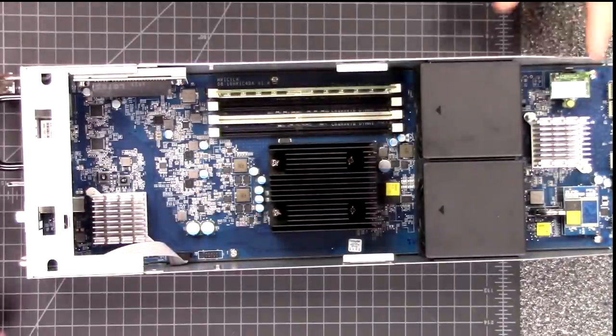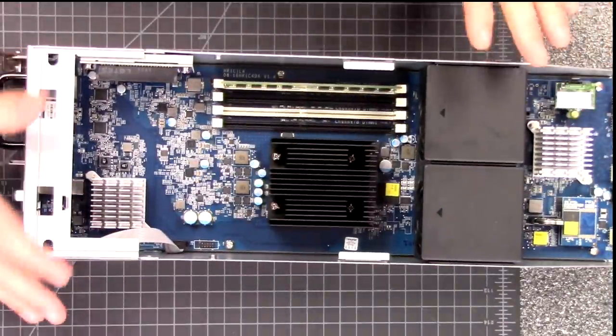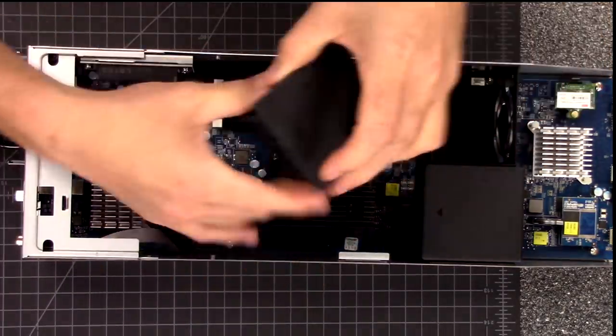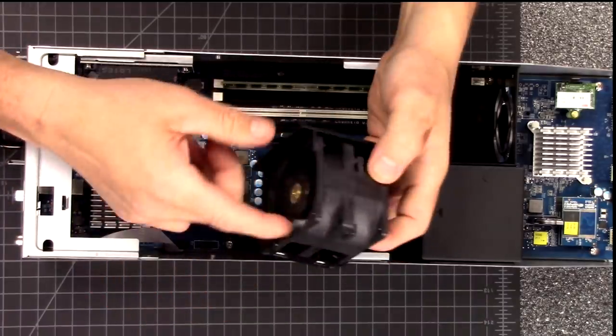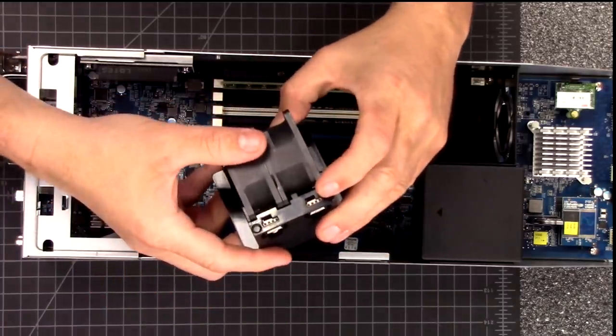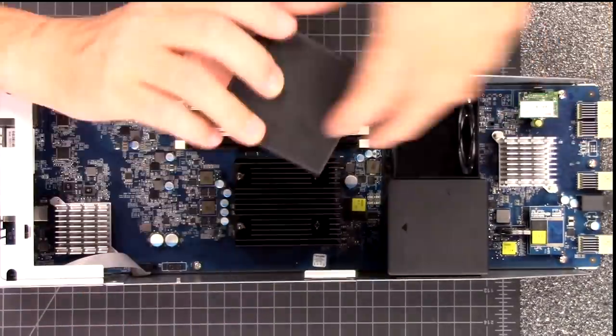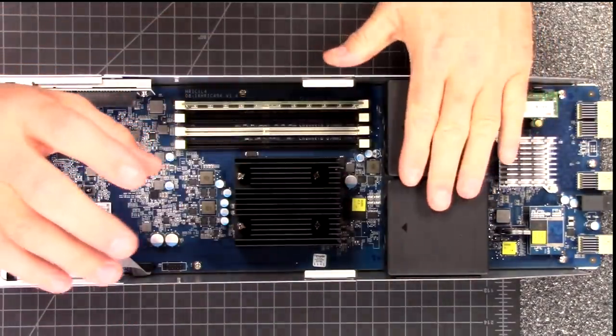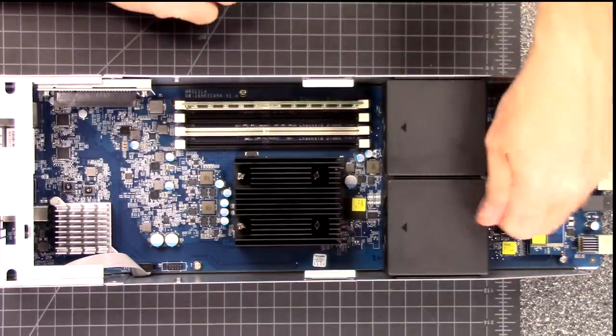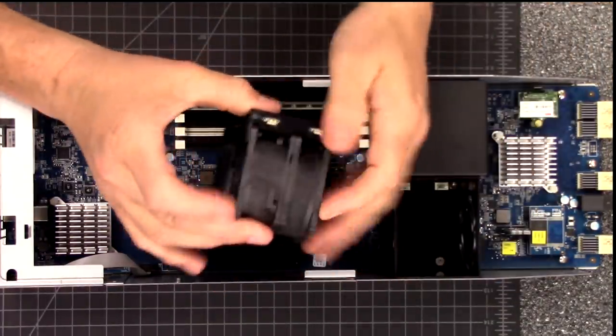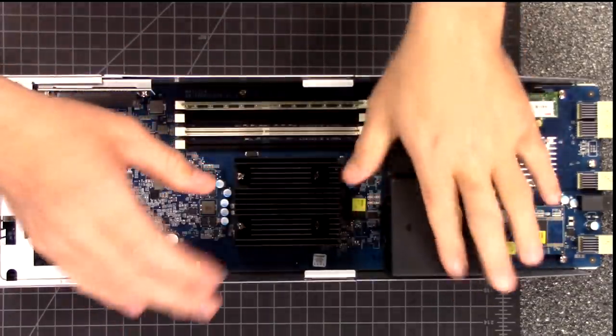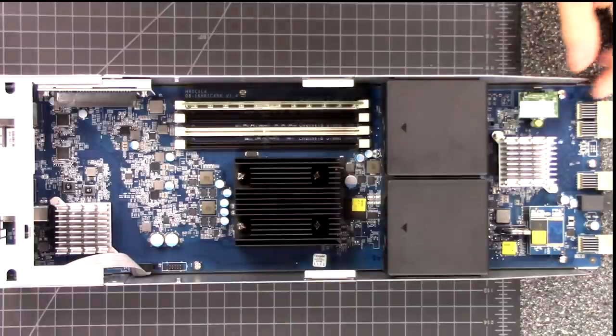To take a closer look at the modules themselves, these lids just snap on and off. That part's tool-less. The fans are in there quite well. Dual fans, one on each side, independently spinning of each other. Edge connectors go right into the base there. They firmly fit in really easy. They have a little arrow on them so you know you've got the airflow right. These are easy to swap. Slide a module out if a fan were to go bad. We have two fans on each side. Airflow's nice and straight through the system.